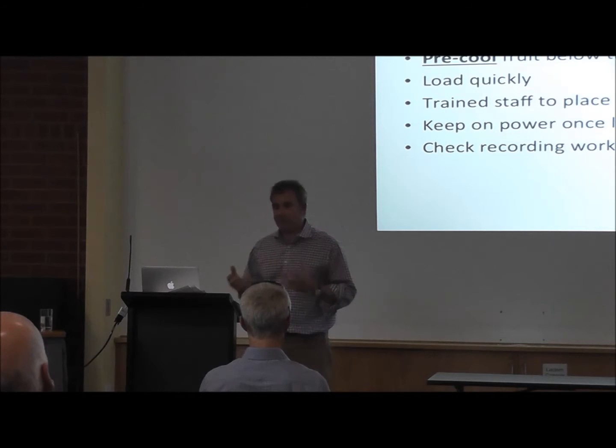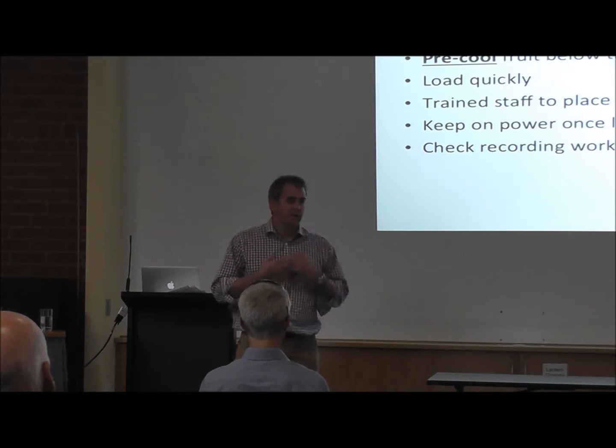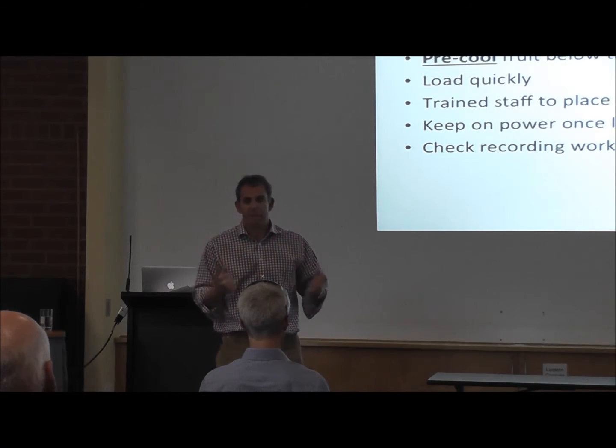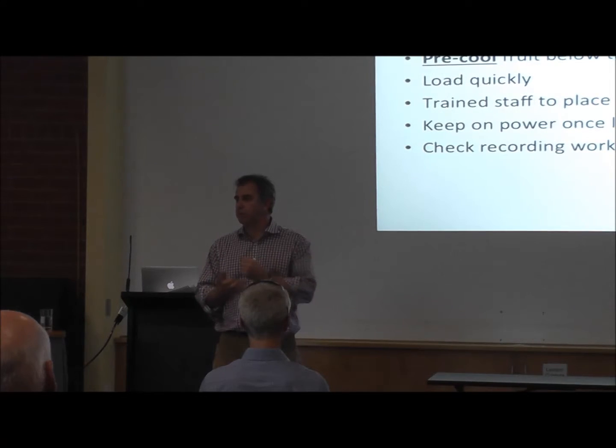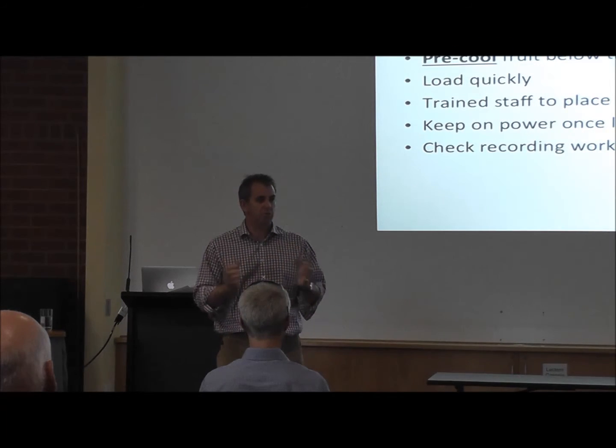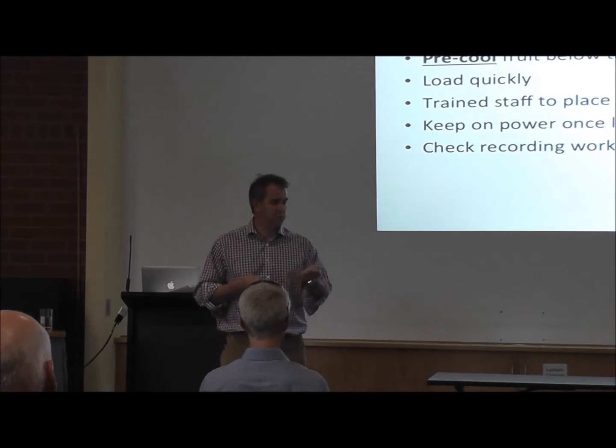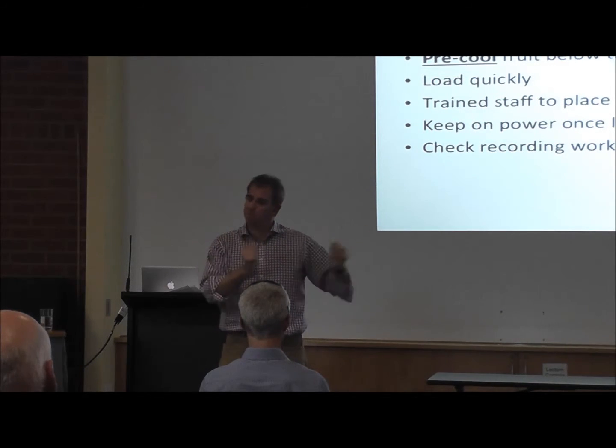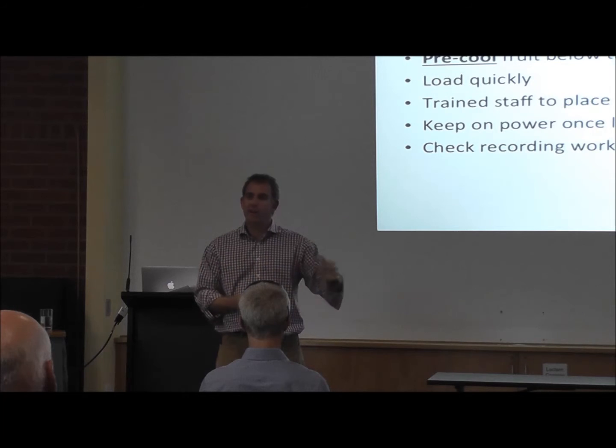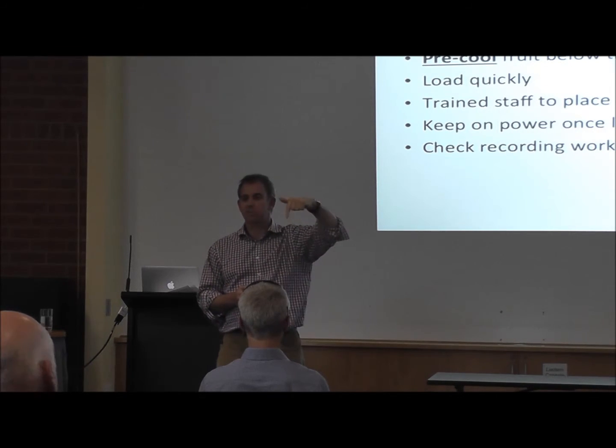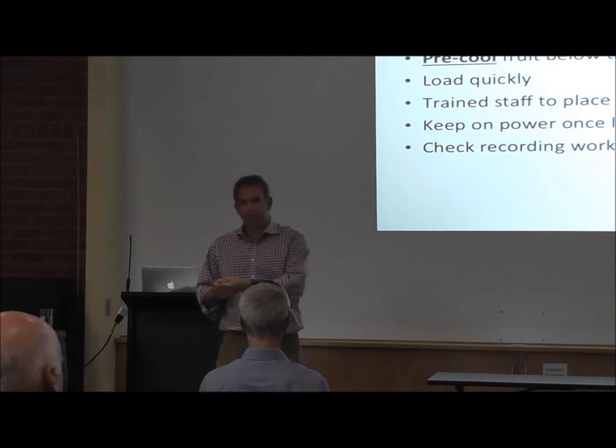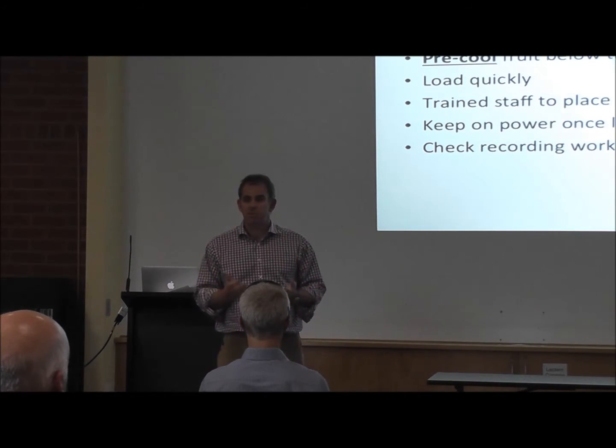I can't reiterate this enough, guys. In our experience, and as the commercial people we work with will tell you, the fruit needs to be properly cold in a pre-cooler — not just walking around the outside, sticking your probe in and saying the fruit on the outside of the pallet is 1 degree, so it's okay. You need to know what the rest of the pallet is like. It's no good having the middle of the pallet at 6 degrees while saying it's fine on the outside, because that's not what achieves success.